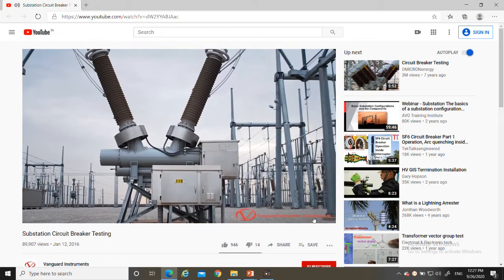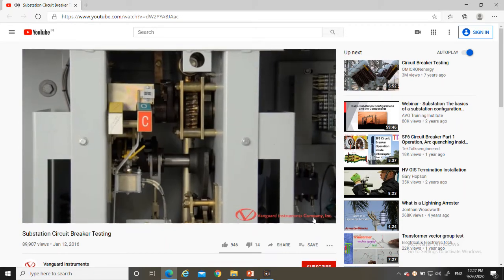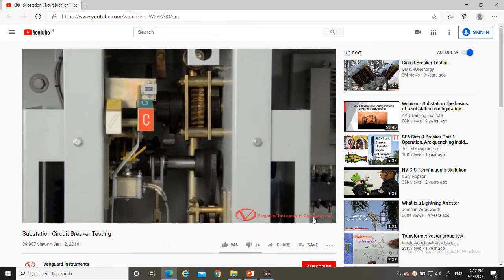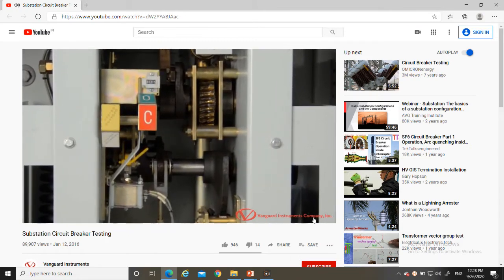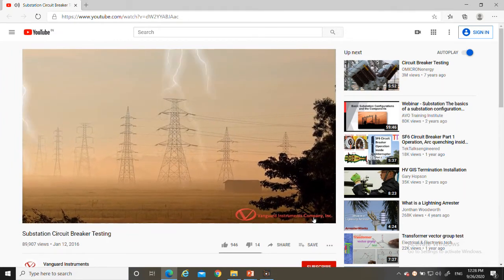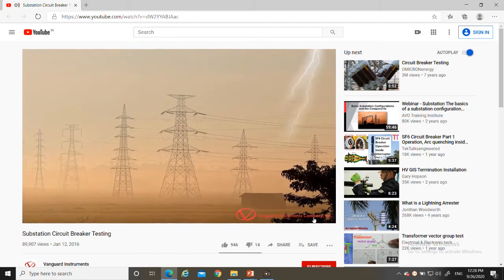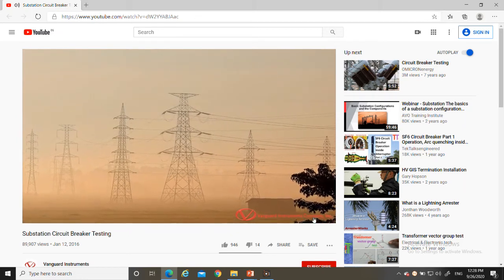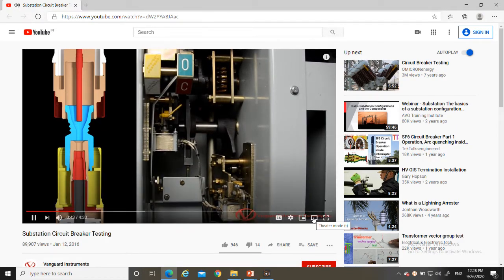Circuit breakers are an important and critical component of the power delivery system. They are mechanical switching devices capable of making, carrying, and breaking current in normal and abnormal conditions. During abnormal conditions such as when lightning strikes a transmission tower, circuit breakers isolate the faulty components to prevent additional damage. Ideally, in the closed position a circuit breaker should act as a perfect conductor, and in the open position as a perfect insulator, able to break the current instantaneously.